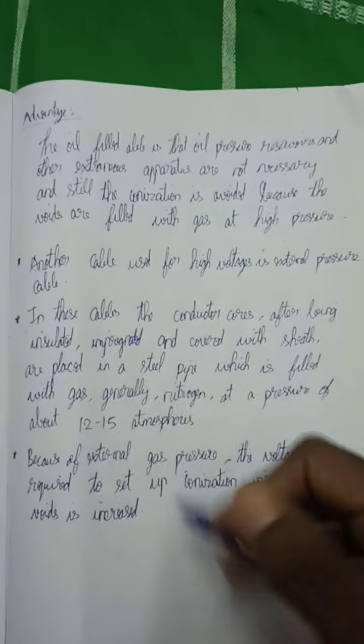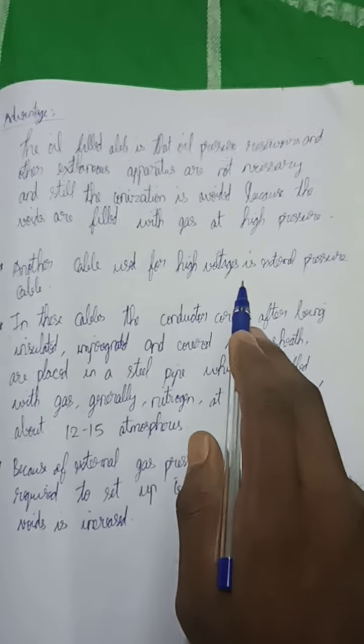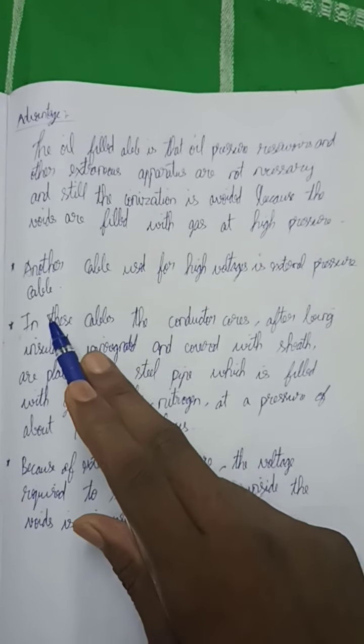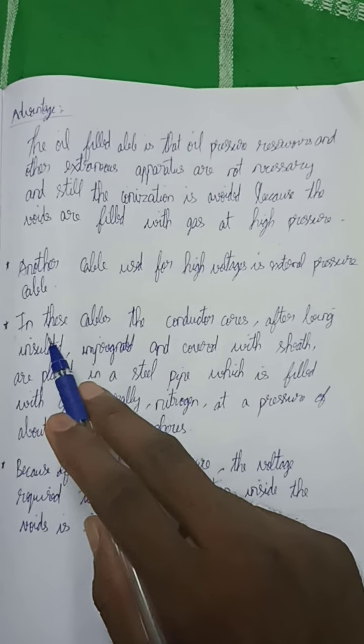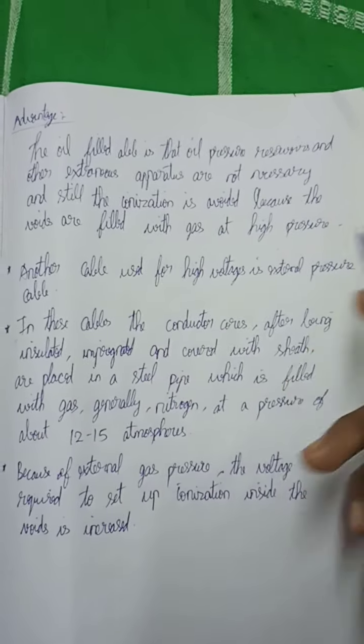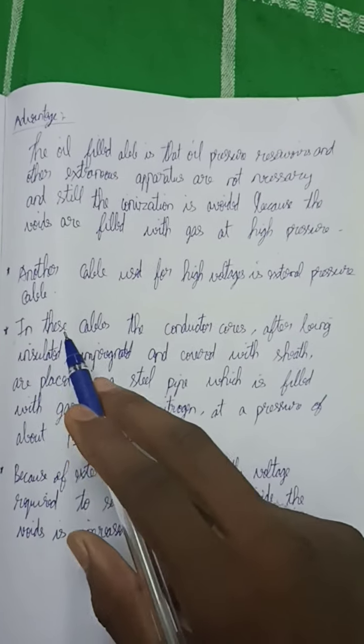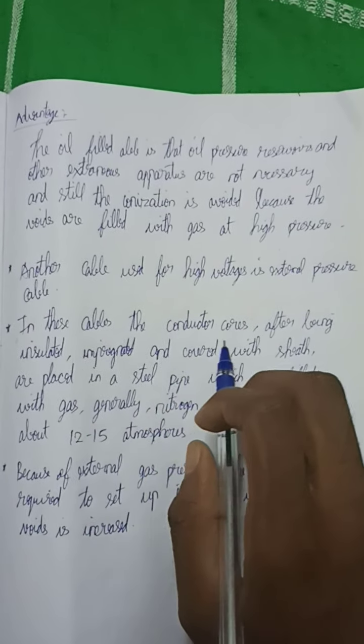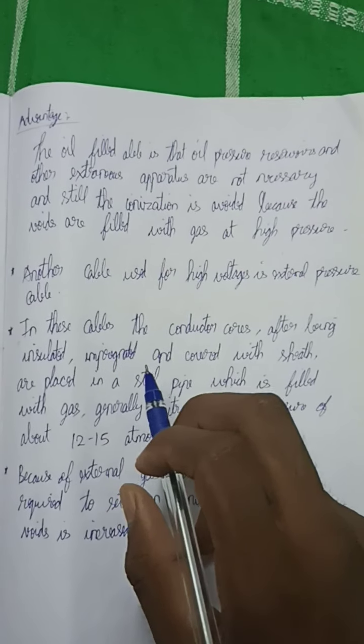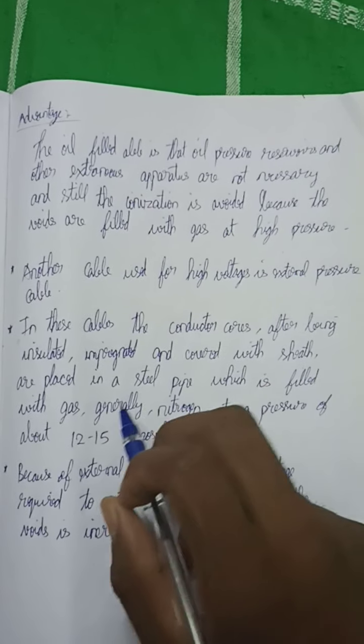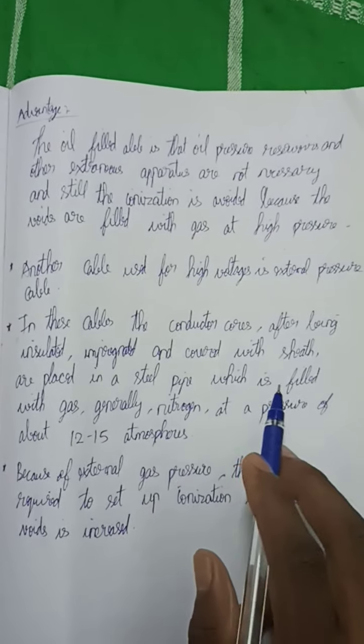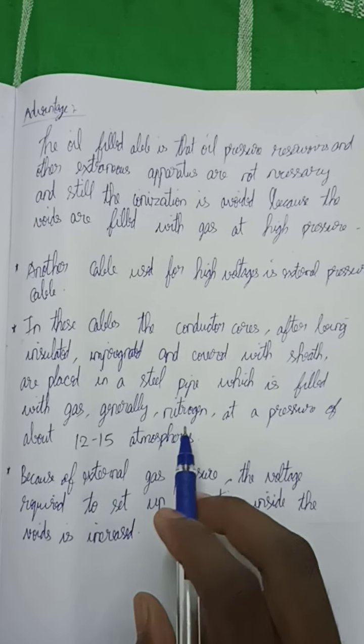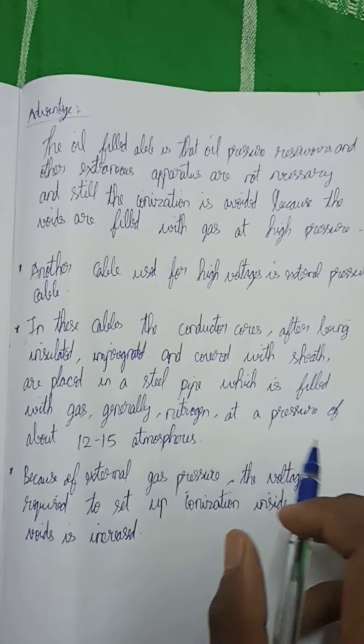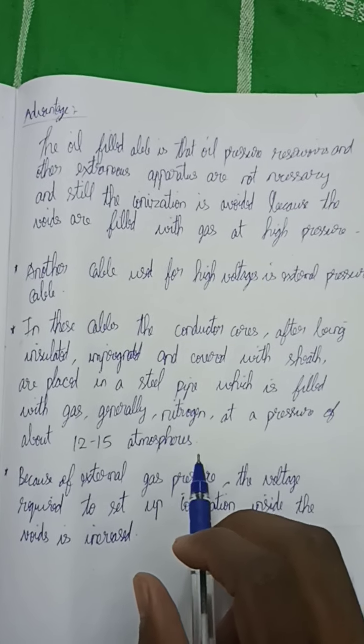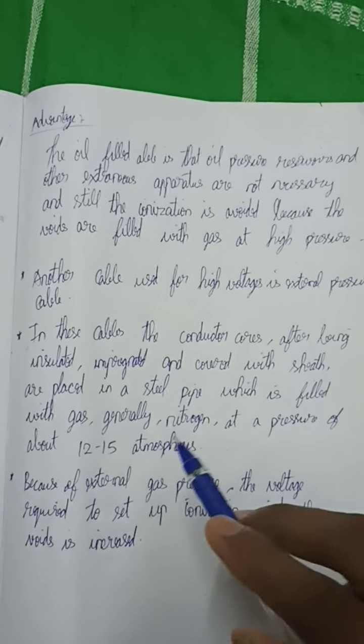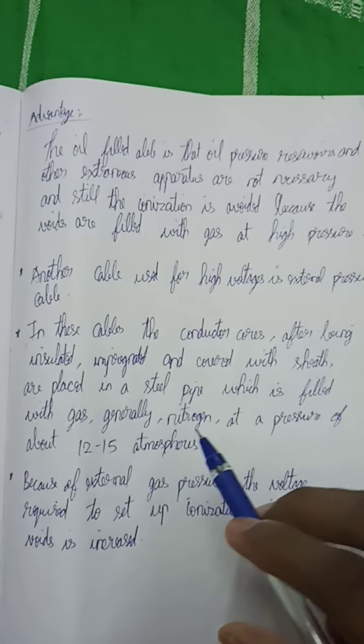And we come to the next. Another cable used for high voltage is the external pressure cable. That is different. In these cables, the conductor cores, after being insulated, impregnated and covered with sheath, are placed in a steel pipe which is filled with gas, generally nitrogen, at a pressure of about 12 to 15 atmospheres.